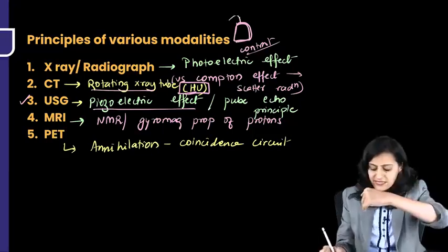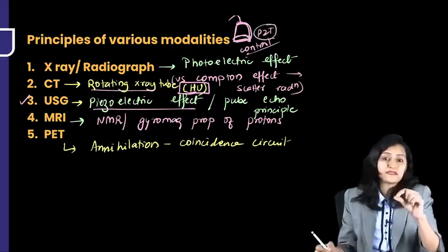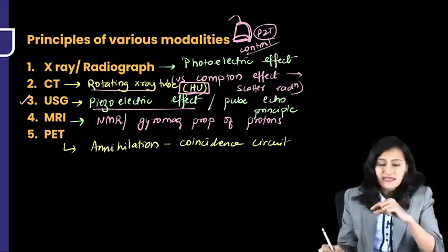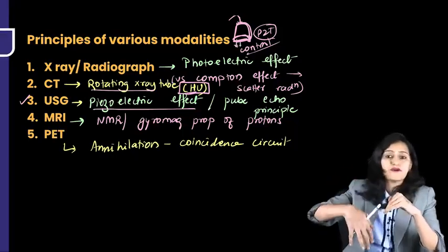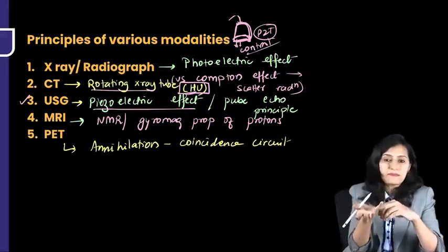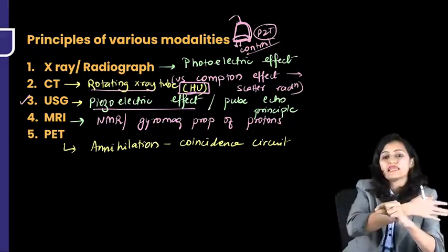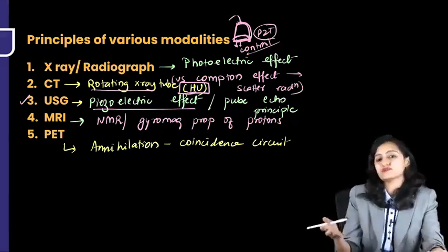We have the electric signal coming in. The crystal here, which is of lead zirconium titanate, has piezoelectric property. So when the electricity comes, it converts this electricity to sound. The sound goes into the patient's body, the sound is reflected back, picked up by this crystal and again converted to electricity. So that is a transducer, converting one form of energy to another.